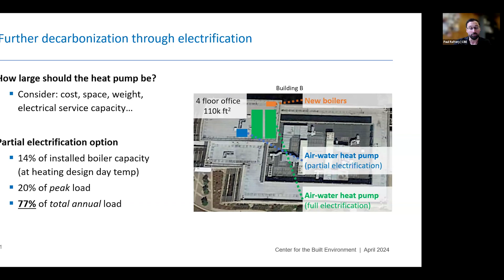And one of the things that's really interesting about heating loads is that they're very skewed distributions. And what I mean by that is most of the time, the building heating loads are quite low. They only very rarely approach the kind of peak heating temperatures, right? We have to design for the coldest day of the year, or the coldest day the building would ever reach, but it's very rare we actually operate in that over the context of a whole year. What that translates to is that a really small heat pump can actually service quite a lot of the annual heating demand in a building. And we saw that in the larger data set that Rupam presented as well, if you want to look at that data in more detail.